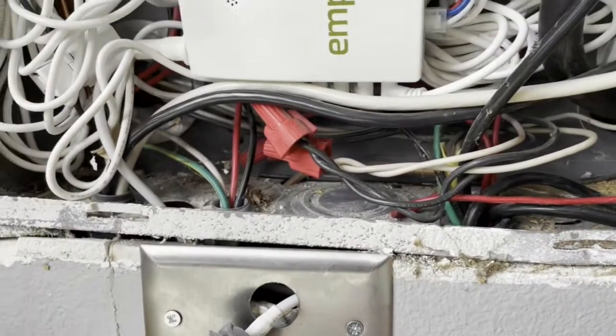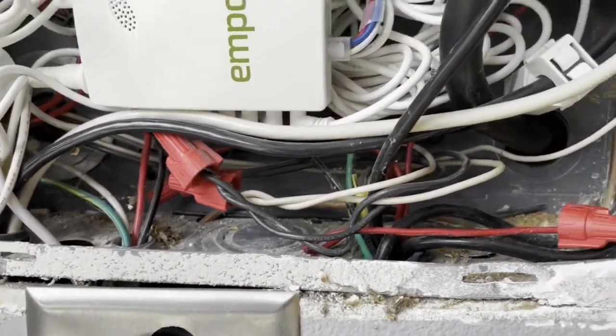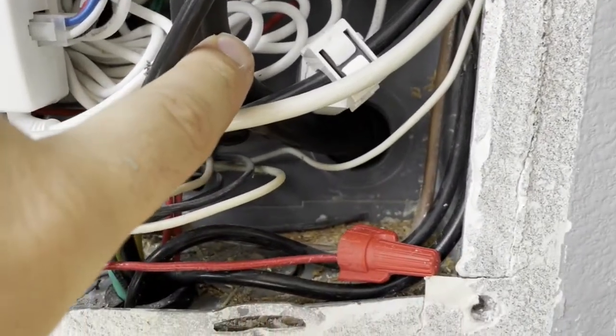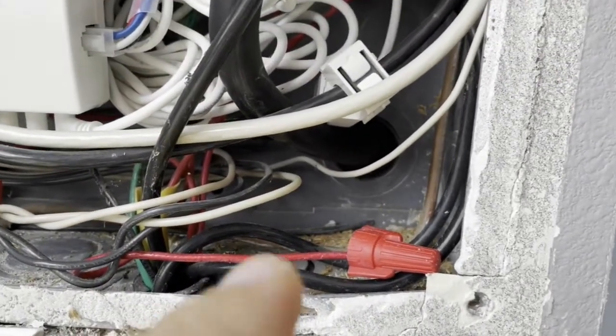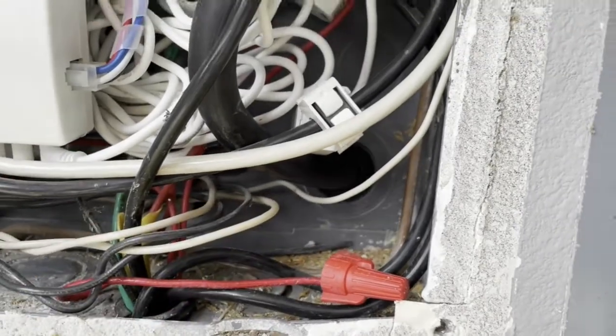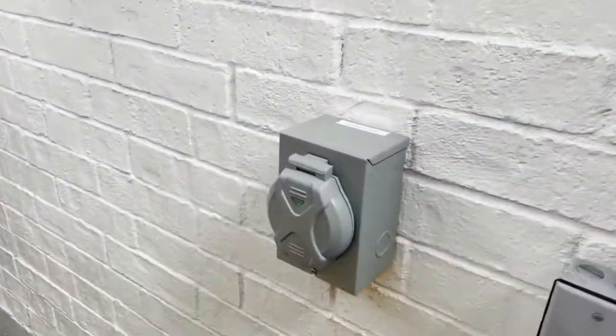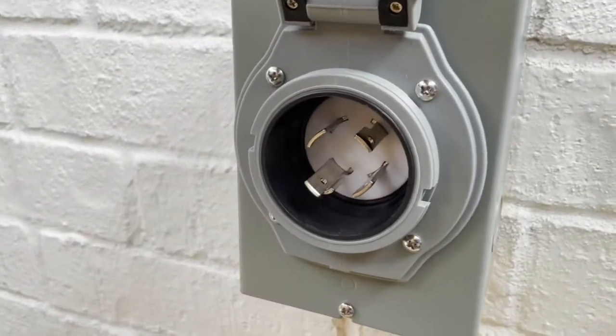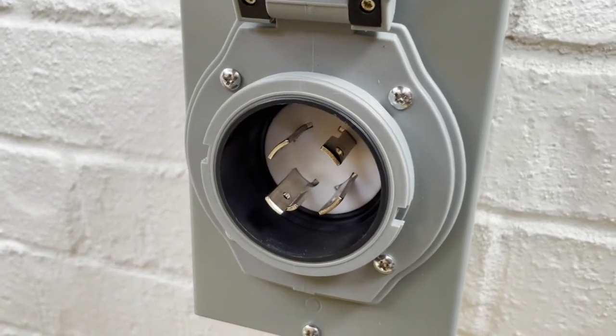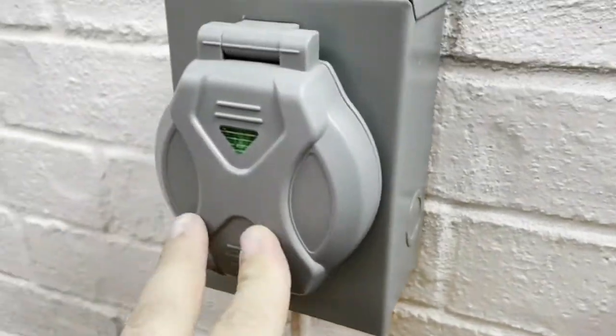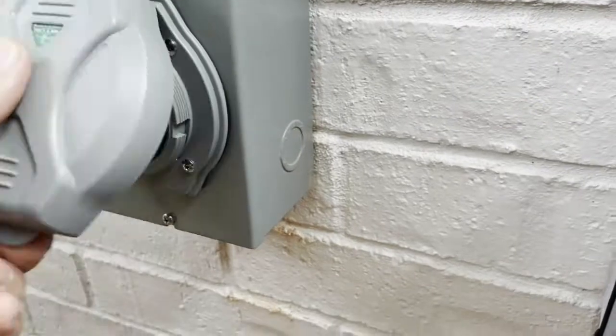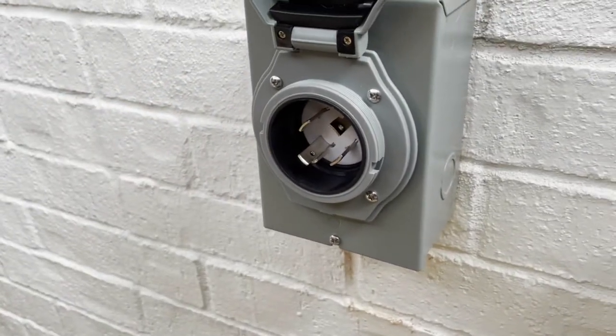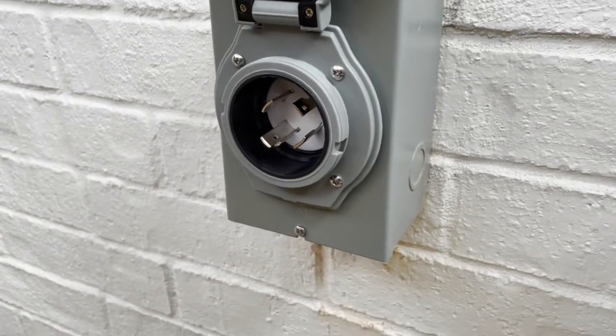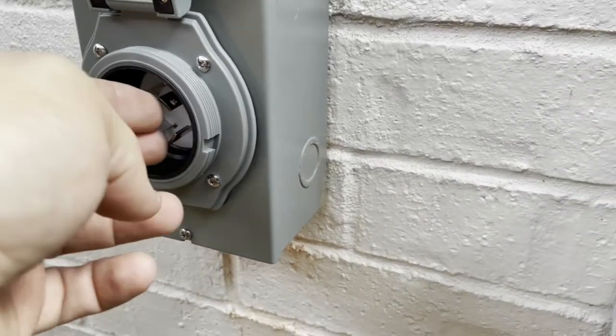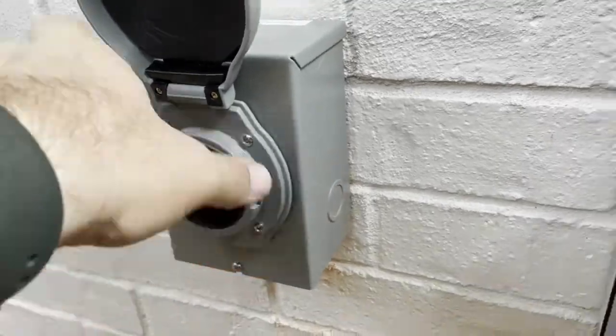As you can see, I just pulled a cable from here, this one, the thick one, which is a 10 gauge cable for 30 amps, and I just went through the brick veneer and also the drywall, and I will show you the outlet now. It comes out here. As you can see, this is a 30 amp 14-30 outlet, so that you can connect your generator here. This one is a good one because it has also a light on it. Of course, this is not live because the generator switch is not on unless you turn off the main power. If you turn off the main power and flip the generator on, then again there will be no power here because there's nothing coming from the grid. So you just plug your generator here.